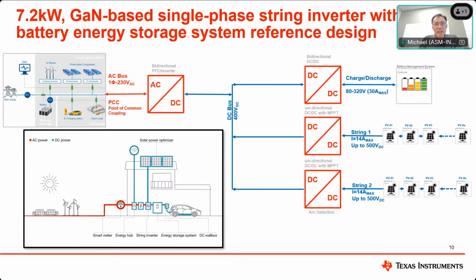So you'll see on the right bottom, 2 PV string inputs, each capable of operating with current up to 14 amps. The maximum open circuit voltage at each string input could be as high as 500 volts. This voltage is only visible when the strings are not loaded.